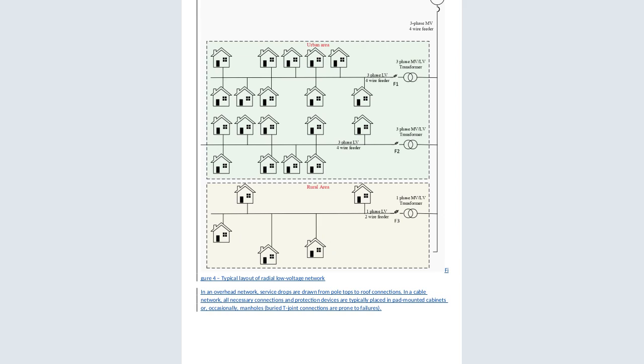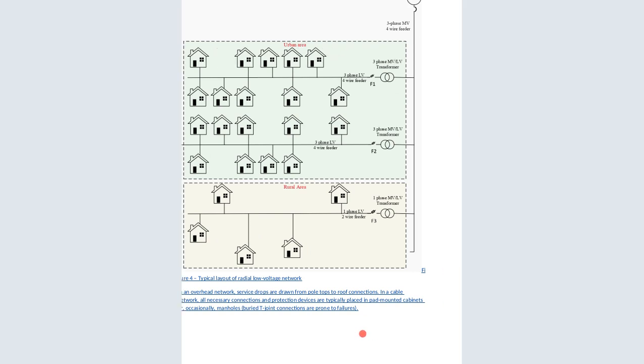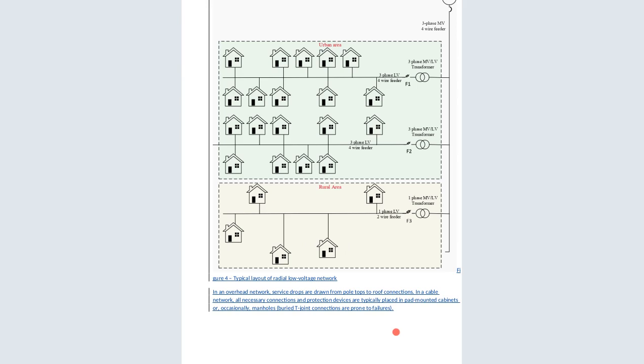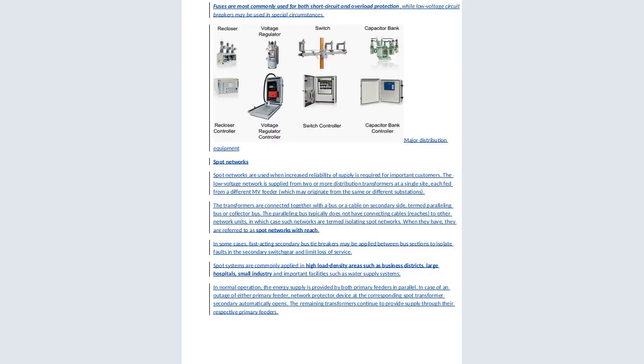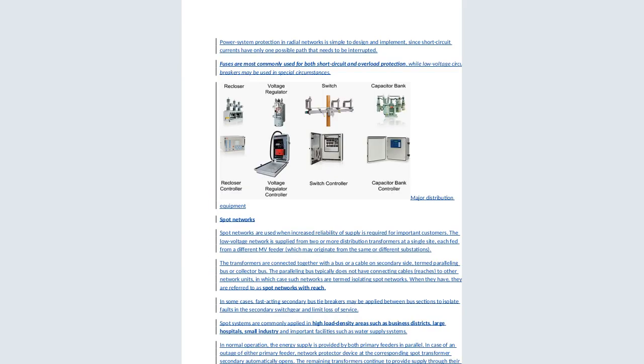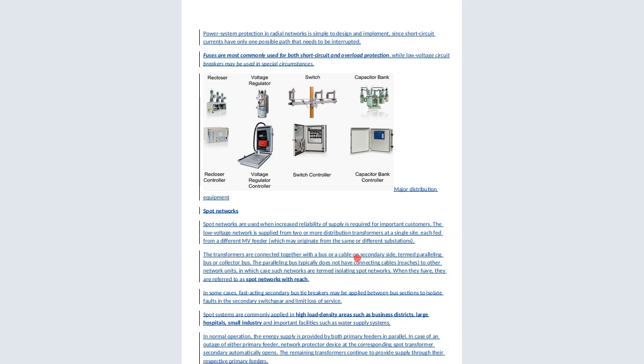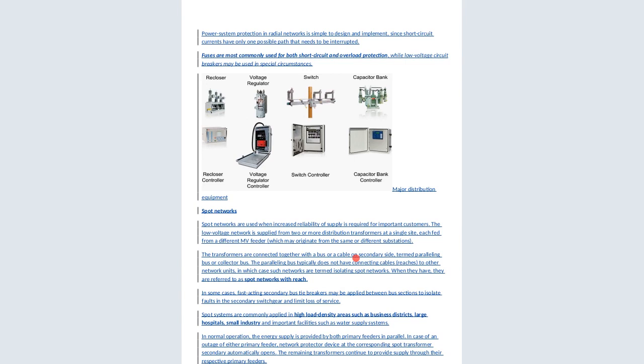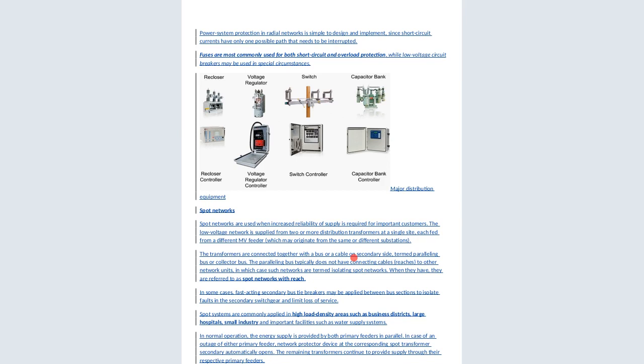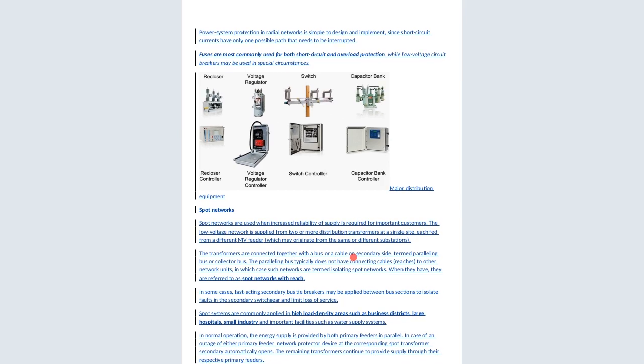In an overhead network, service drops are drawn from pole tops to roof connections. In a cable network, all necessary connections and protection devices are typically placed in pad-mounted cabinets or occasionally manholes. Buried T-joint connections are prone to failures. Power system protection in radial networks is simple to design and implement, since short-circuit currents have only one possible path that needs to be interrupted.